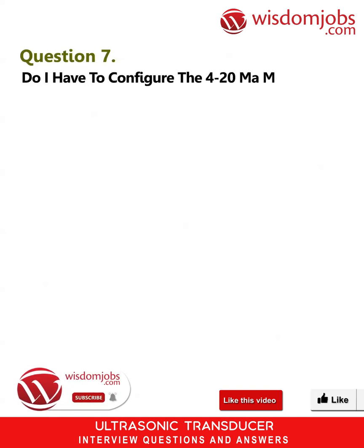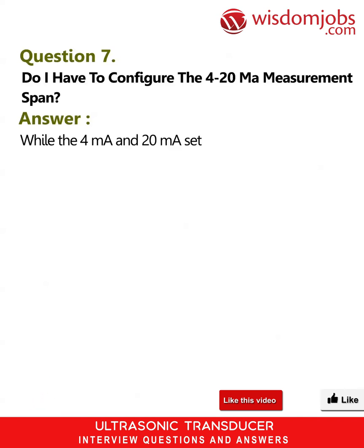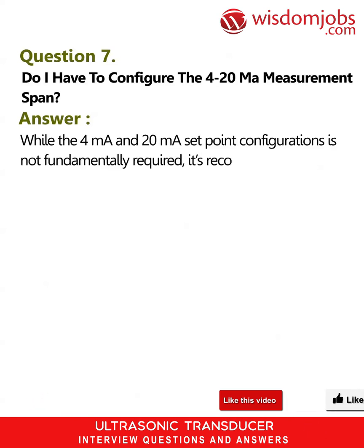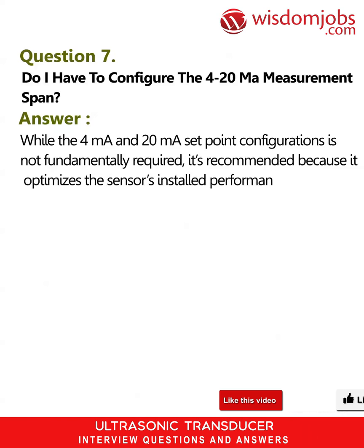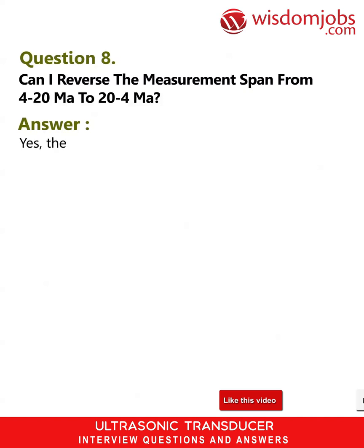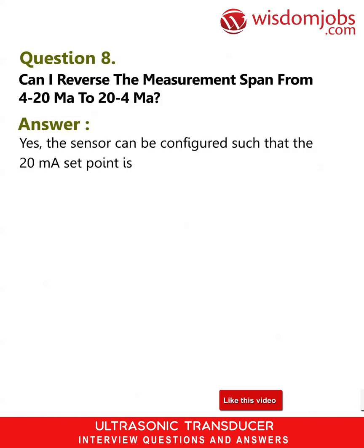Question 7. Do I have to configure the 4 to 20 mA measurement span? Answer. While the 4 mA and 20 mA set point configuration is not fundamentally required, it's recommended because it optimizes the sensor's installed performance. Question 8. Can I reverse the measurement span from 4 to 20 mA to 20 to 4 mA? Answer. Yes, the sensor can be configured such that the 20 mA set point is empty and the 4 mA set point is full.